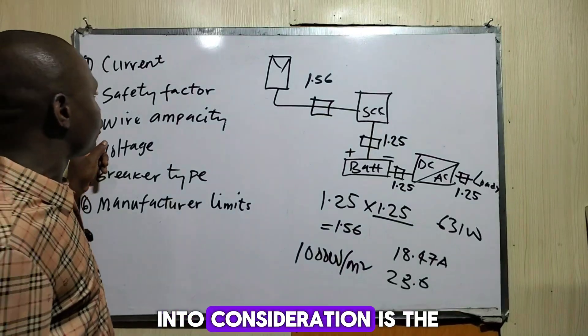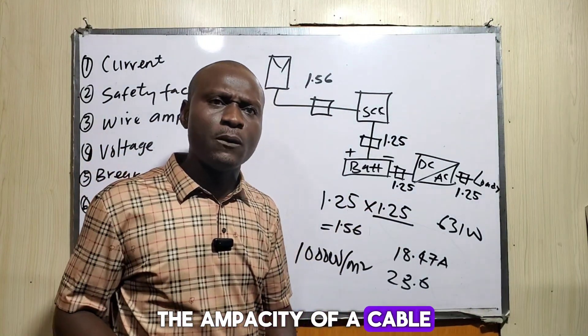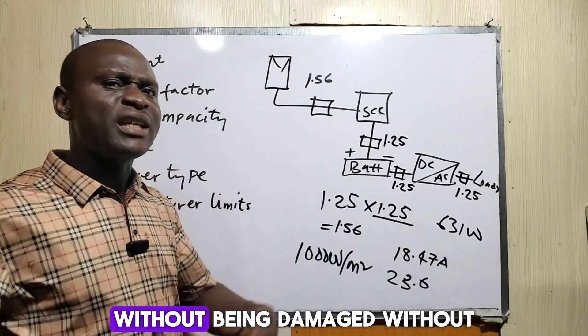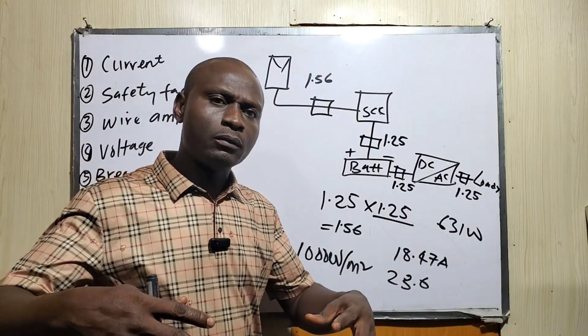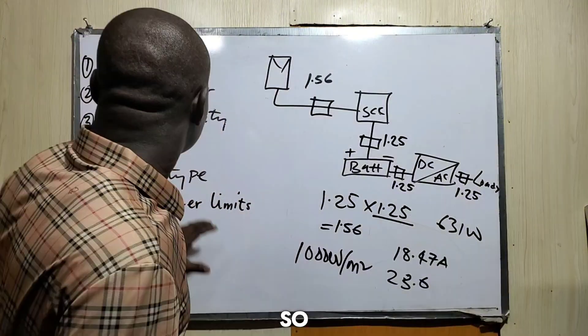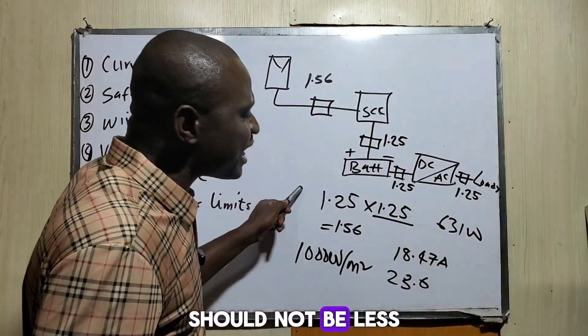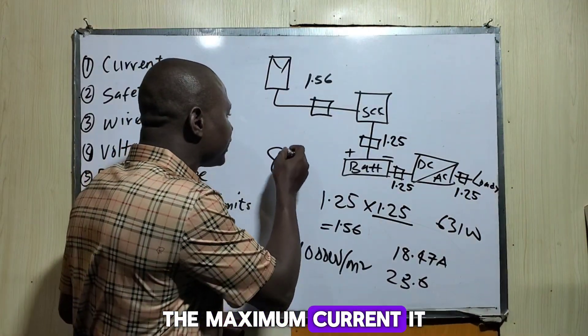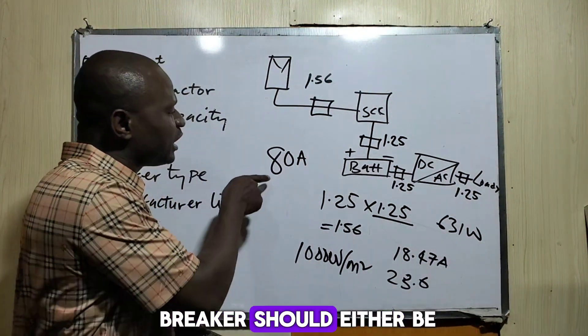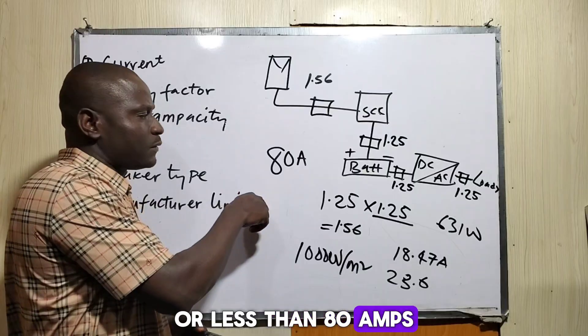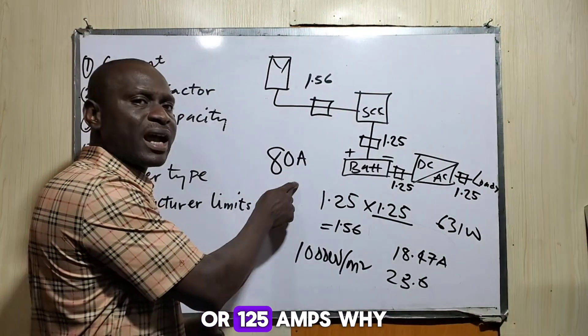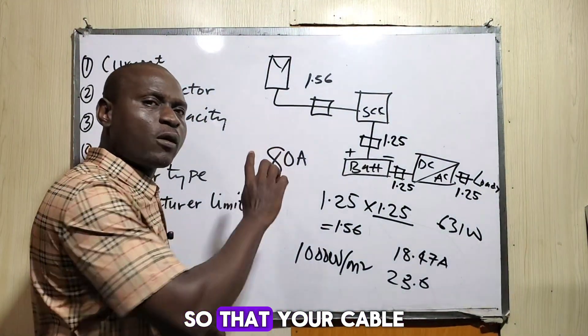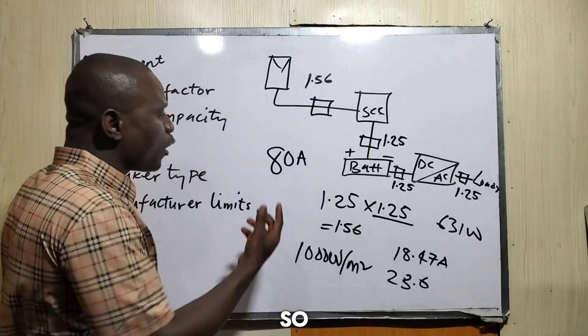The third factor is wire ampacity. The ampacity of a cable is the maximum amount of current a cable can carry continuously without being damaged or experiencing overheating. The ampacity of the cable should not be less than the size of your breaker. If your cable's ampacity — the maximum current it can carry — is 80 amps, the size of your breaker should be 80 amps or less.